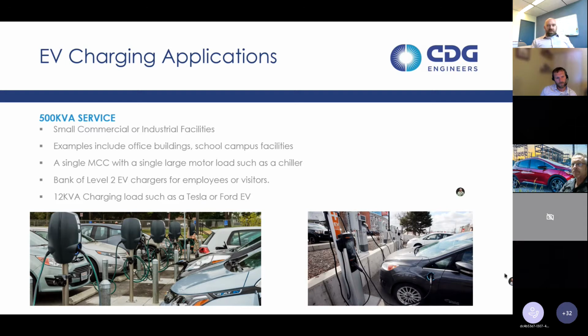We modeled this in ETAP, which is a power analysis software. The first example I did was for a 500 kVA size service - imagine a small commercial building, maybe a college campus building or city hall at a municipality, maybe a light industrial facility. They might have a single MCC or larger panel boards and maybe a large motor load like a chiller or something like that. They want to put in a bank of level 2 EV chargers for employees or visitors, or maybe city vehicles that they've converted to electric.